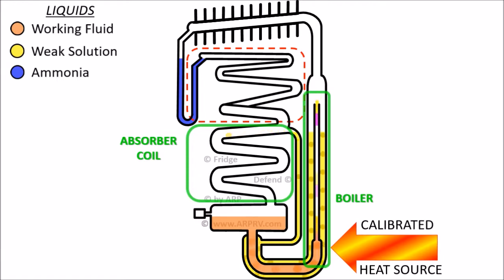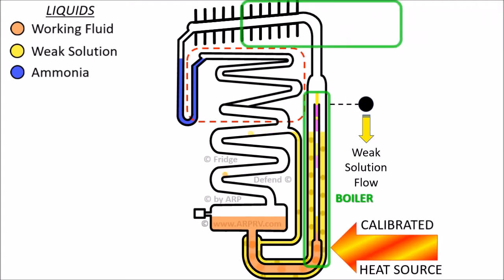The weak solution flows by gravity back to the absorber coils. We will return to the flow of the weak solution within the absorber coils. Going back to the top of the pump tube, the ammonia gas rises up to the condenser. The condenser changes the ammonia gas into liquid ammonia by cooling the gas.